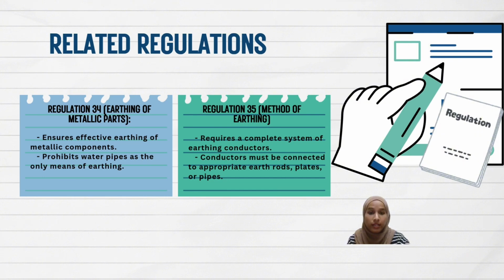This part is about related regulation. To address the identified non-compliance, we refer to two key regulations from the Electricity Regulation 1994. The first is Regulation 34, which ensures effective earthing of metallic components, prohibiting the use of water pipes as the sole means of earthing. Next is Regulation 35, which requires a complete system of earthing conductors connected to appropriate earth rods, plates or pipes to provide a safe and reliable grounding system.